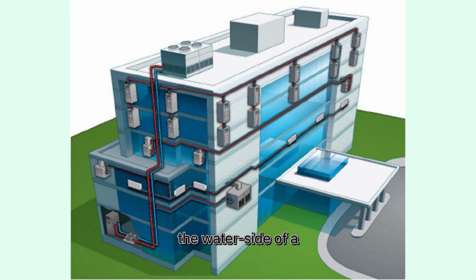Now let's look at the water side of a WSHP system. Unlike a traditional chilled water system, the WSHP water loop is simple and contains only three major components: a cooling tower, a boiler, and pumps. First, the cooling tower. Its job is to reject excess heat during the cooling season. The preferred choice is a closed-circuit cooling tower, or CCCT. A CCCT has an internal heat exchanger built in, so there's no need for a separate plate and frame heat exchanger. It protects the system water from contamination, reduces maintenance, and minimizes pumping energy.